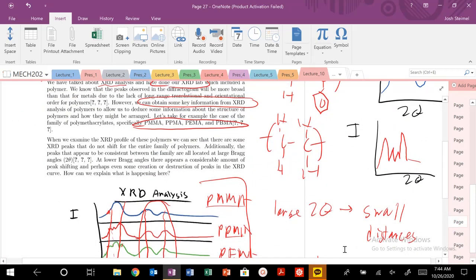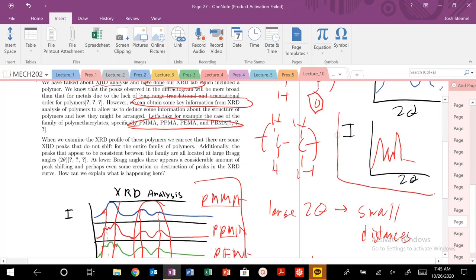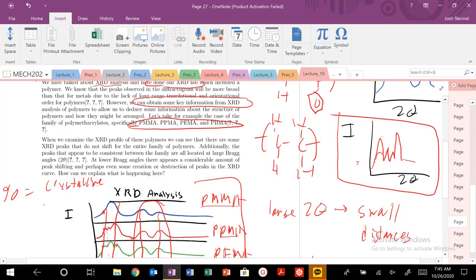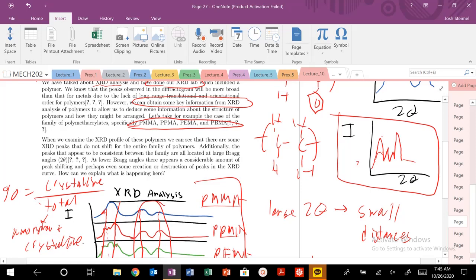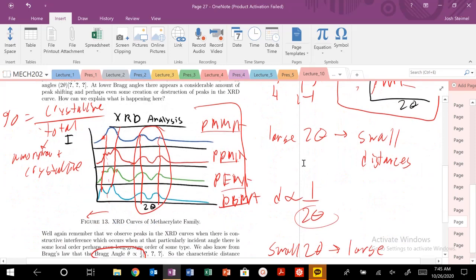Furthermore, you can get quantitative as well. If you have a semi-crystalline material, you can run curve-fitting software to see the relative amorphous contribution and the relative crystalline portion in each peak, and deduce percent crystallinity by looking at the crystalline contribution as a percentage of the total area—which is the amorphous plus crystalline portions. Most XRD machines now have software that can help with this.